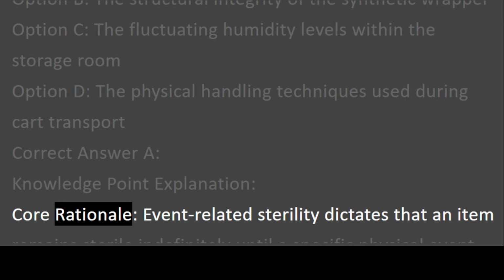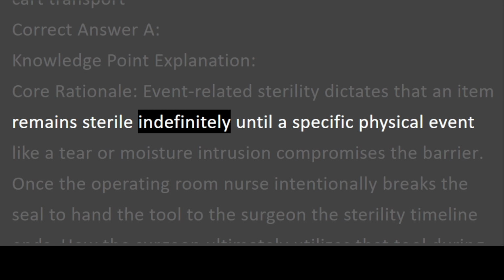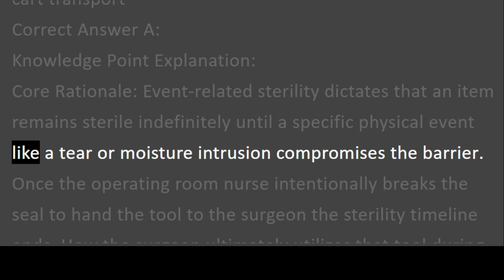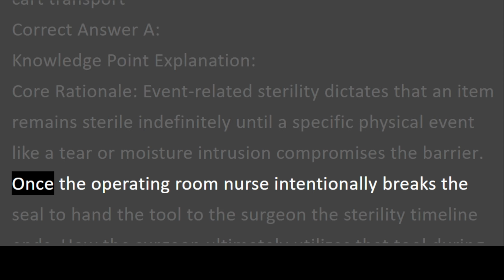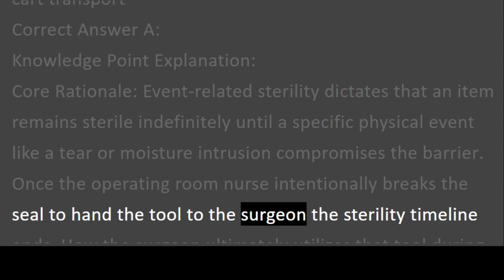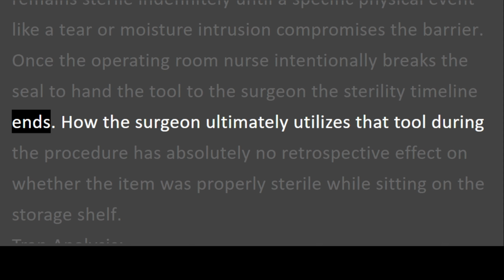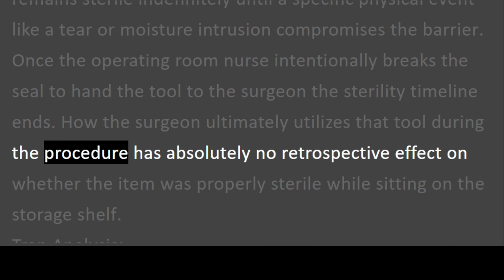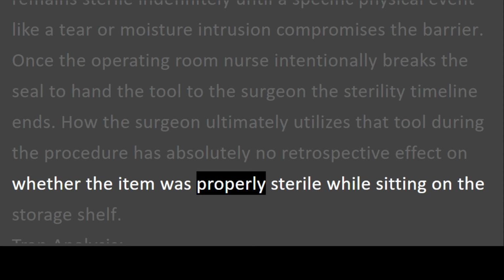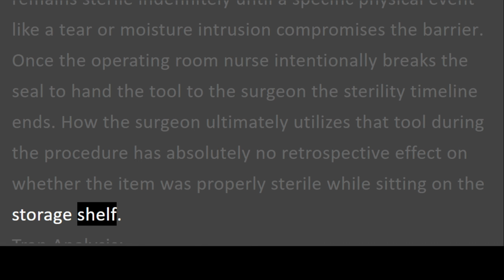Core rationale. Event-related sterility dictates that an item remains sterile indefinitely until a specific physical event like a tear or moisture intrusion compromises the barrier. Once the operating room nurse intentionally breaks the seal to hand the tool to the surgeon, the sterility timeline ends. How the surgeon ultimately utilizes that tool during the procedure has absolutely no retrospective effect on whether the item was properly sterile while sitting on the storage shelf.